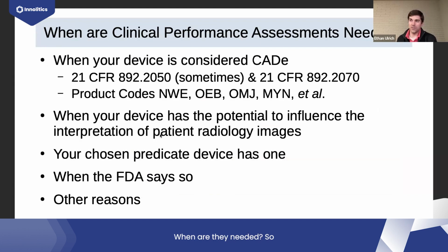When are they needed? Just getting into the weeds on the regulatory side, the FDA does say that for 21 CFR 892.2050, sometimes it is required, and more often for 892.2070, it is required. And they do list out specific product codes, where these are CADe devices, that they are required, but there are additional ones, like an LLZ potentially, that could require a clinical performance assessment.